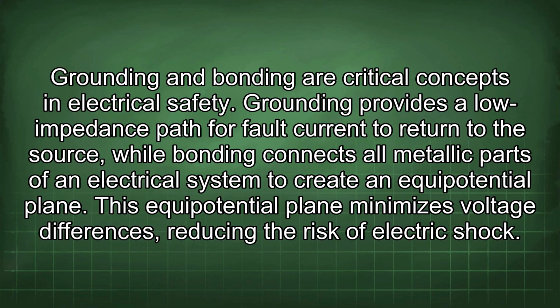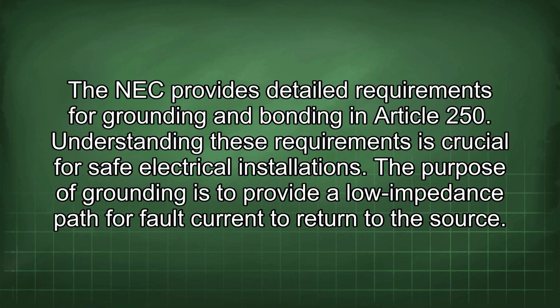Grounding and bonding are critical concepts in electrical safety. Grounding provides a low impedance path for fault current to return to the source, while bonding connects all metallic parts of an electrical system to create an equipotential plane. This equipotential plane minimizes voltage differences, reducing the risk of electric shock. The NEC provides detailed requirements for grounding and bonding in Article 250. Understanding these requirements is crucial for safe electrical installations.